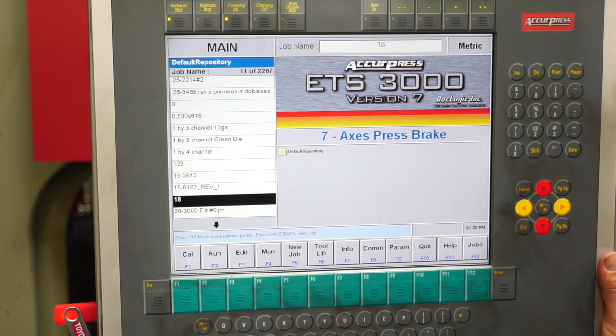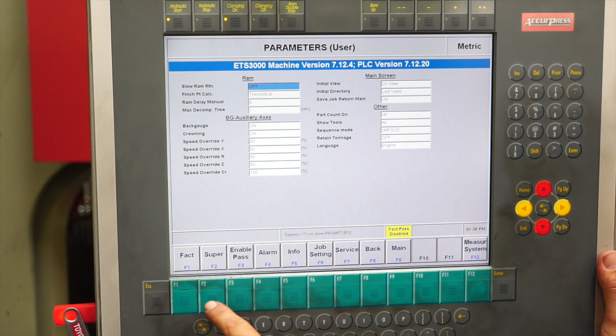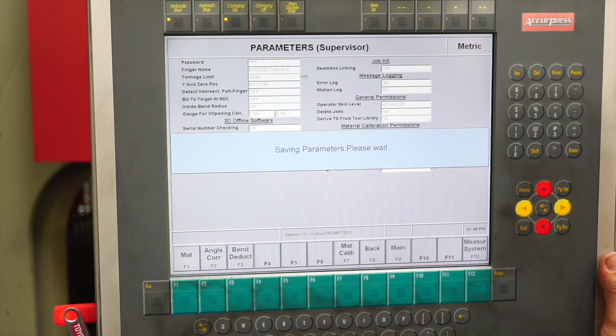Okay, to start, we're gonna press the parameter button. From there we're gonna hit the super button, and then material calibration. Now we're gonna select the material we're gonna calibrate, and in this particular case, A36 sheet steel. Hit OK. Now we're gonna enter the gauge or type in the actual value.